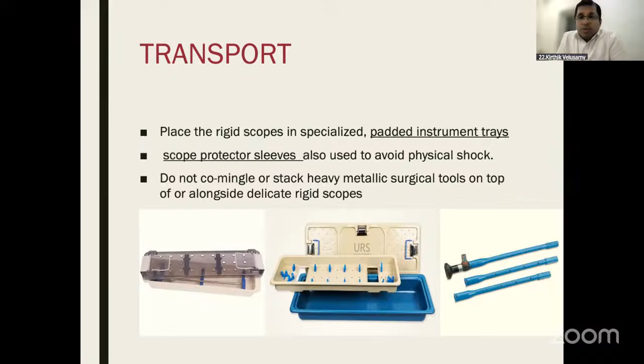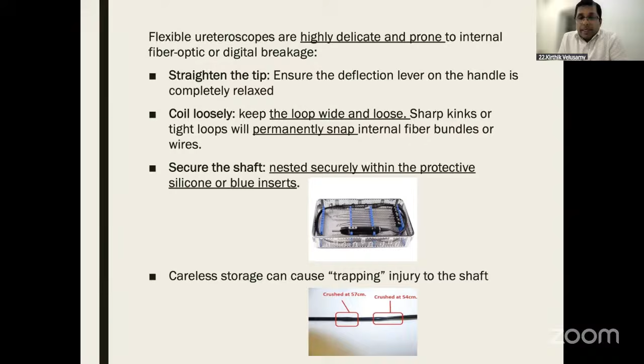Once rinsed and dried, we put the instrument in a padded tray, and scope sleeves are used to avoid physical shock. We should not stack one over the other, to avoid damage to the instruments. Regarding the flexible scopes, we make sure that the tip is straight and it is coiled loosely to avoid permanent snapping of the internal fiber bundles. It is secured safely with the silicone or blue inserts. Otherwise, it will cause trapping injury to the shaft.